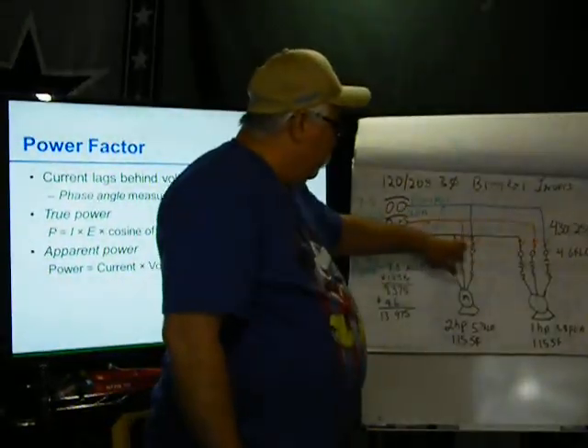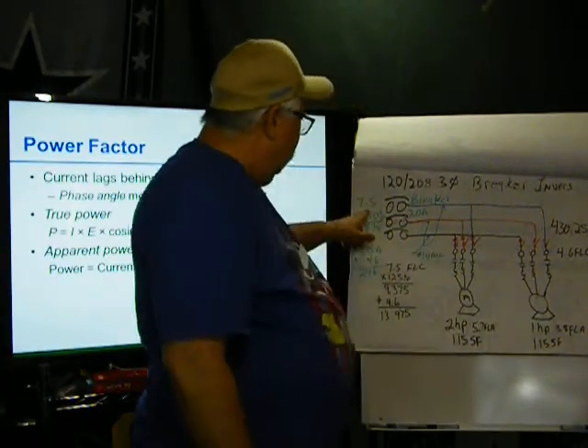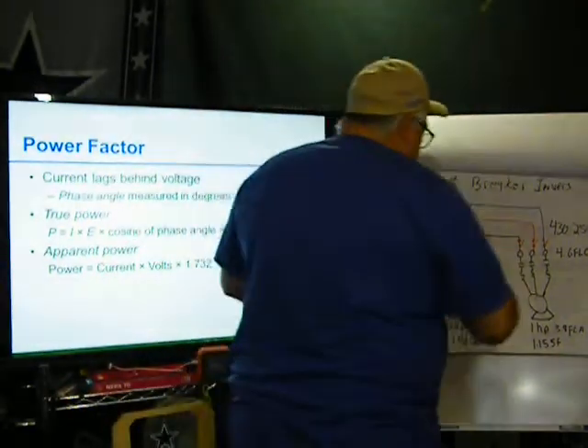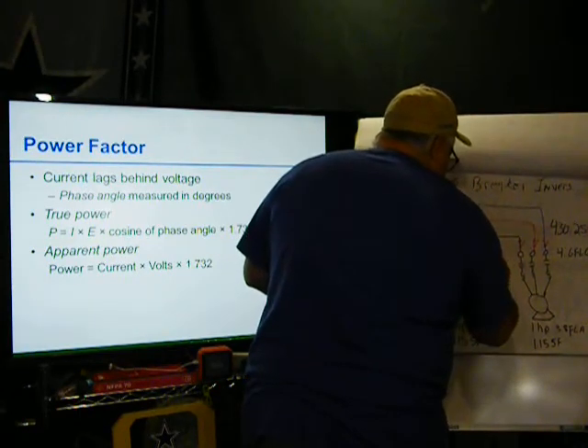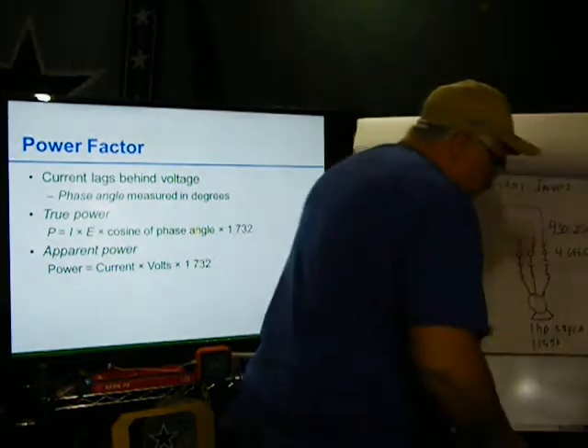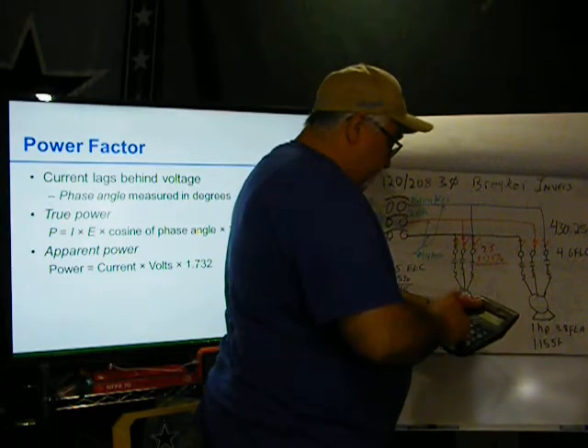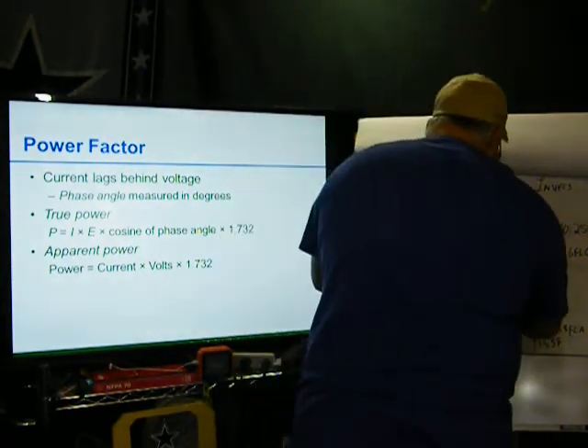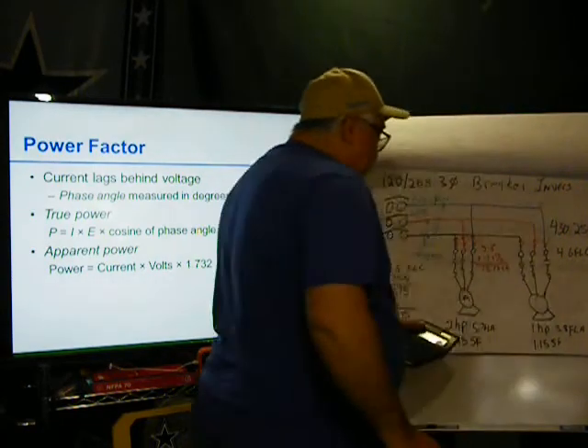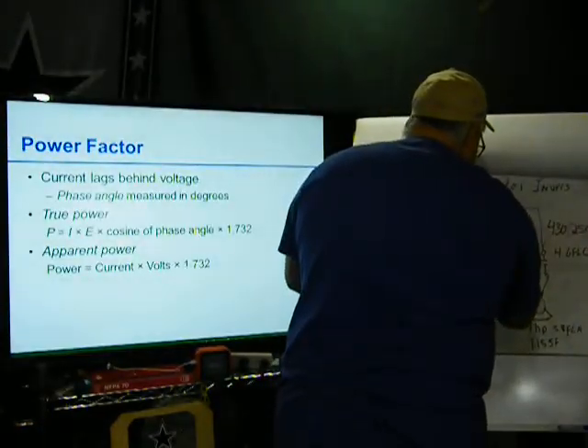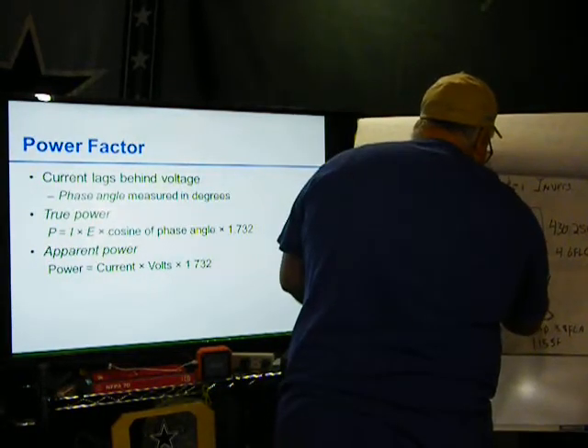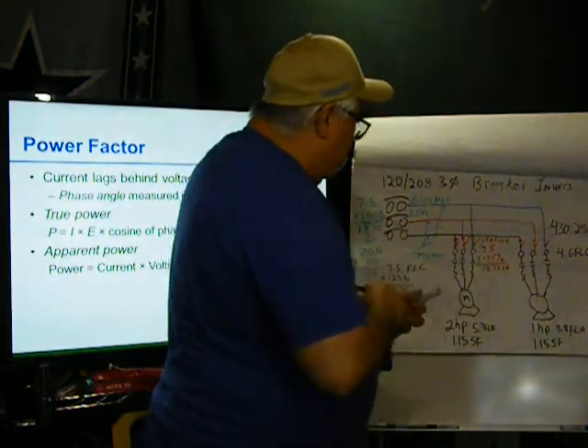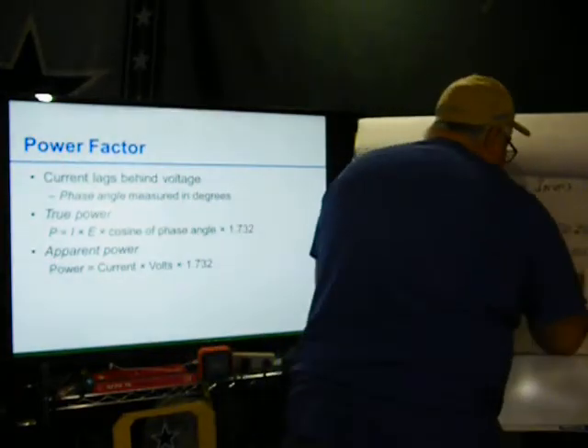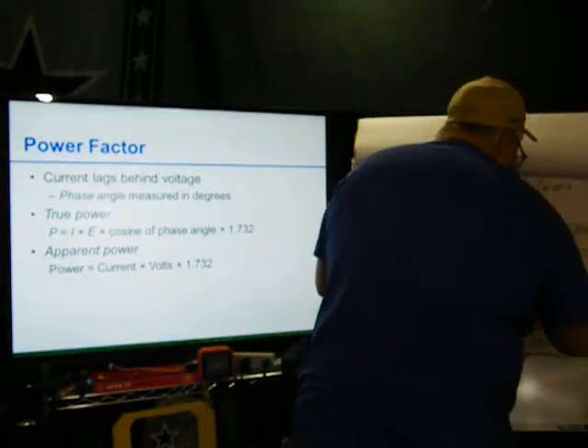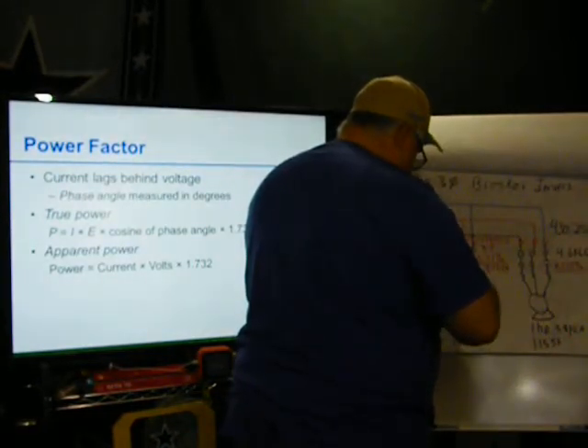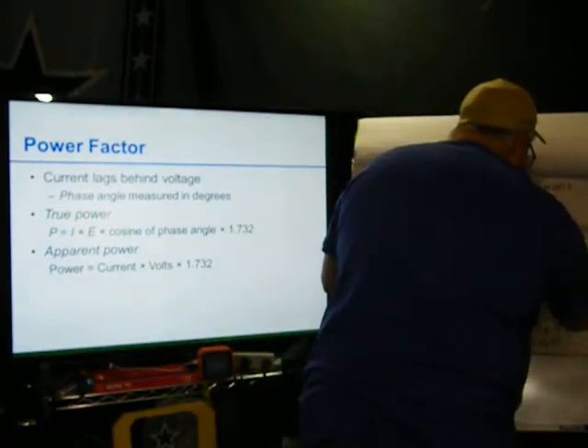Now when we go to find this breaker here, I would get that 7.5, say these are time delay fuses, and that would be multiplied by 175%. So 7.5 times 175% is 13.125 amps. So here would be a 15 amp fuse. And then over here, again, times 175% is 8.05, 15 amp fuse.